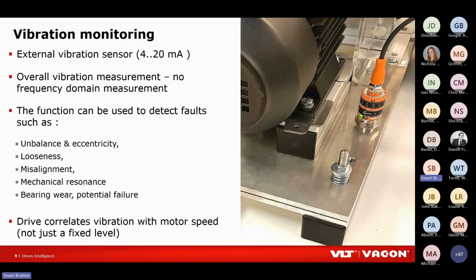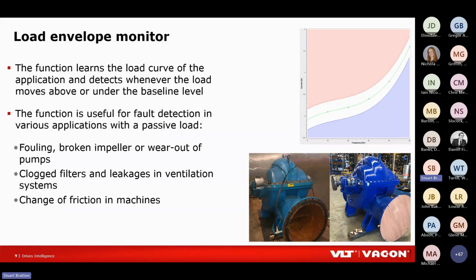But the important thing really, as I've mentioned a couple of times, is this correlation against speed. We're not just capturing a fixed level. We're matching the vibration level or the sensor signal against the motor speed. I'll come back to that and show why that's important near the end of the presentation.